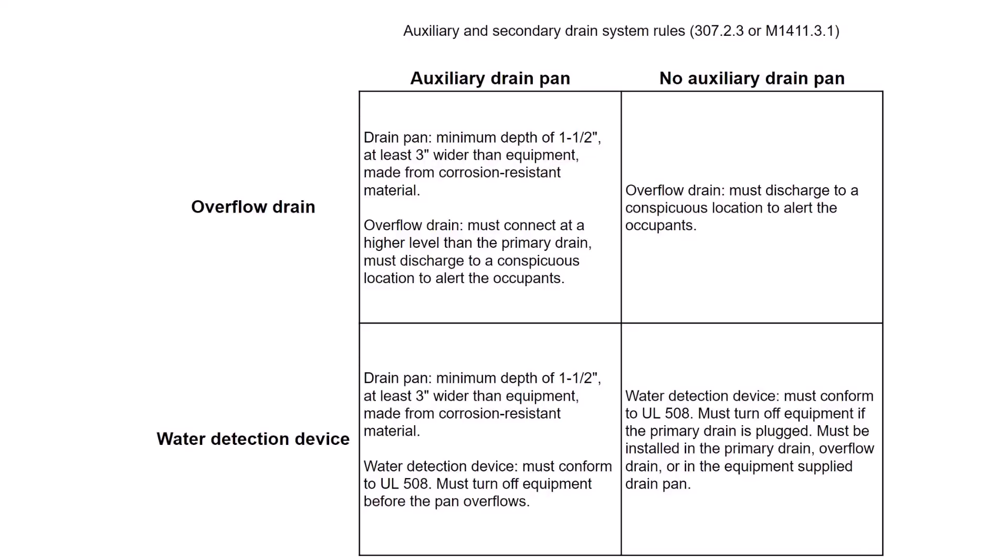So there are four ways to do this. I made up a little chart, and you break it down. It's either you have an auxiliary drain pan, or you don't have a drain pan, or you can have an emergency overflow drain, or you can have a shutoff device. You can have any combination of those four components and it's going to satisfy code requirements to protect your structure.